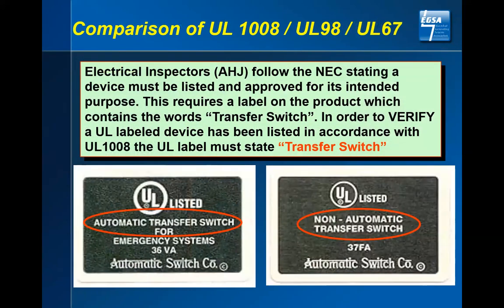When you look at it, one of the other things that you folks may run into is an AHJ, the authority having jurisdiction. Many times that is your electrical inspector. In the California area, there is what's referred to as OSHPD, and that is part of the hospital requirements that they are the authority having jurisdiction. Throughout some of the other areas is another hospital organization that will oversee things. But you need to know who it is.